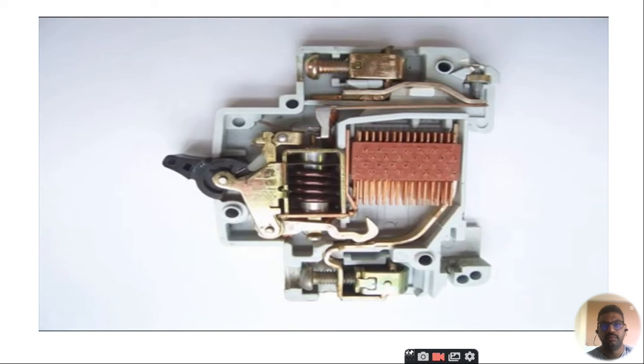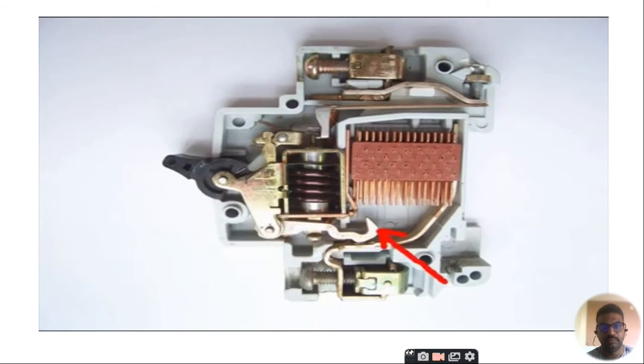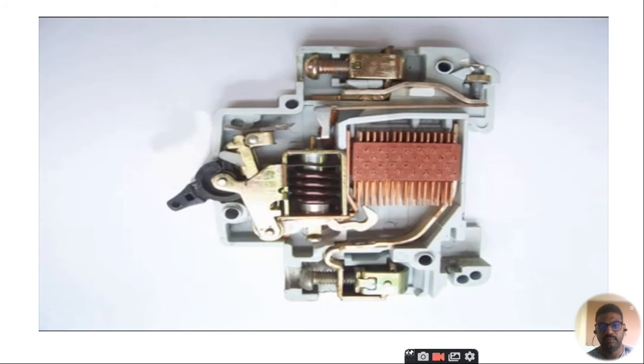If overcurrent flows for long time through this MCB, the bi-metallic strip becomes overheated and hence it is deformed. This deformation of bi-metallic strip causes displacement of latch point. The moving contact is arranged by means of spring pressure with this latch point such that little displacement of latch causes release of spring and makes moving contact move for opening the MCB.